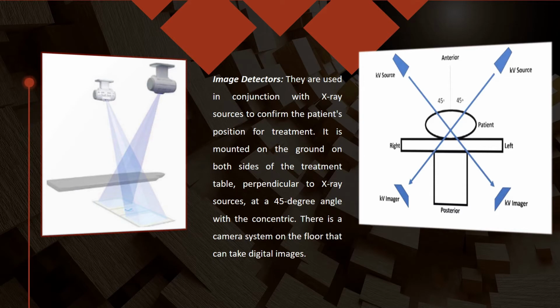Image detectors. They are used in conjunction with the X-ray sources to confirm the patient's position for treatment. They are mounted on the ground on both sides of the treatment table, perpendicular to the X-ray sources, at a 45-degree angle with the concentric. And there is a camera system on the floor that can take digital images.